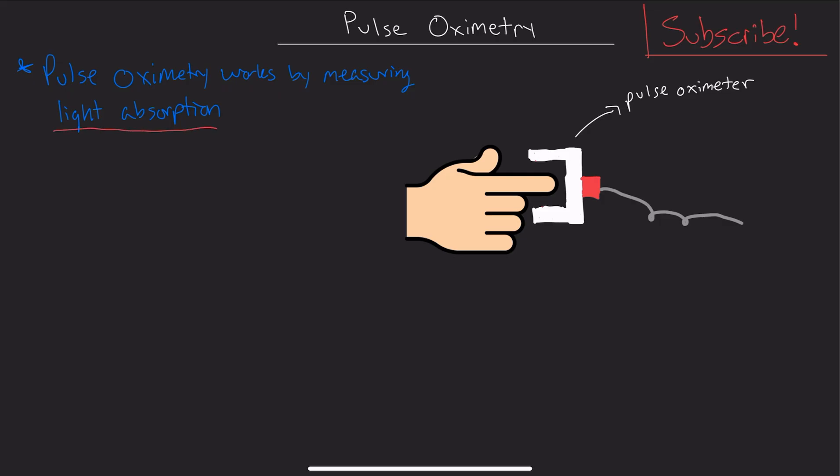How it does this is there's a probe on one side of the pulse ox and a sensor on the other. This probe is going to send two different wavelengths of light through the finger, the ear, wherever you have it connected, to the sensor.